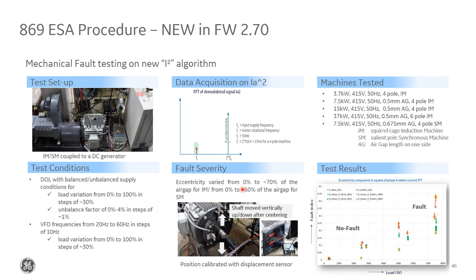Just to give you an idea, we have done extensive testing during the last year on this I-squared algorithm. This main test was done by varying the eccentricity of the motors and seeing how the mechanical fault component of the ESA function picked up. We've tested this update on both induction and synchronous motors of varying sizes and VFD-driven motors. We previously did not have ESA certified for use on synchronous motors or VFDs, but with this new algorithm in 2.7 onwards, we do support all of those.